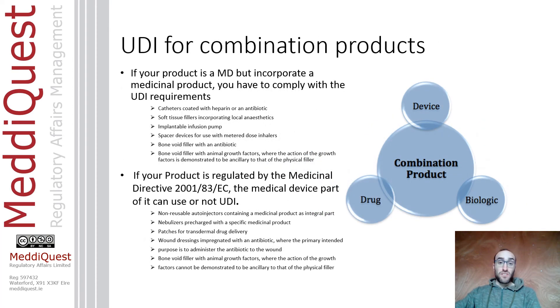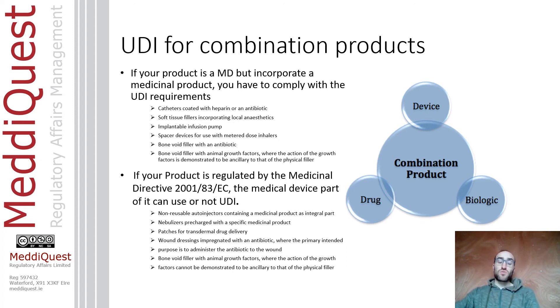For combination products, you need to understand if UDI is applicable. If your product is a medical device that incorporates a medicinal product, you must comply with UDI requirements, and examples from the Medical Device Coordination Group are provided. However, if your product is regulated by the medicinal directive and the medical device part incorporates a medicine, UDI is not mandatory.